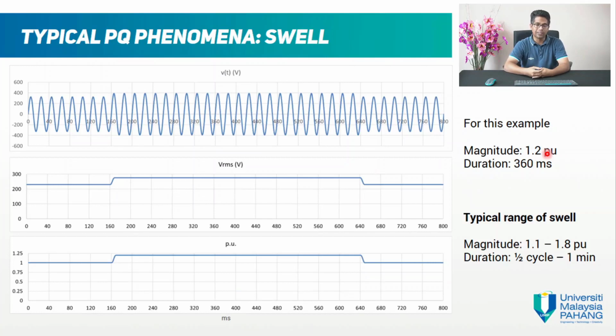Another thing is swell. Okay. Sag is when the voltage gets lower. Swell is when the voltage gets bigger. Okay. So this is a typical swell. In this case, it's 1.2 pu. Okay. And the duration is 360 milliseconds. Okay, and swell goes from 1.1 to 1.8 pu, and the duration range is similar to voltage sag, half cycle to 1 minute.